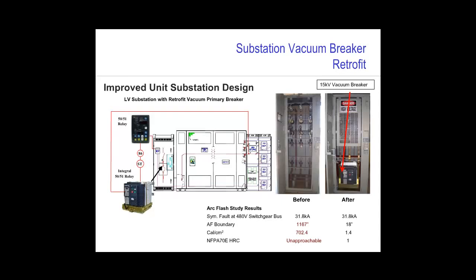One via a 50/51 overcurrent device that's mounted in the primary assembly itself, which actually trips the breaker through a lockout 86 relay and a shunt trip, and the other via the integral trip unit in the breaker connected to secondary CTs in the secondary switchgear bus.